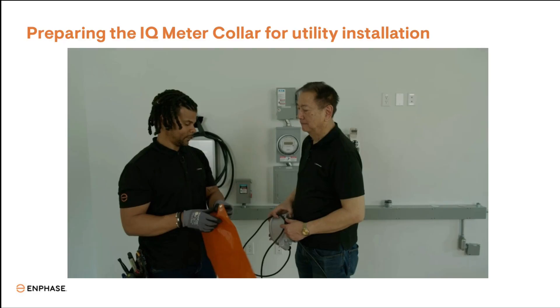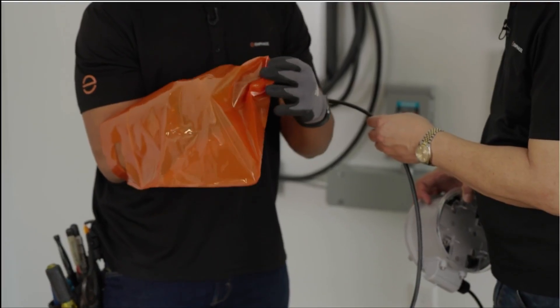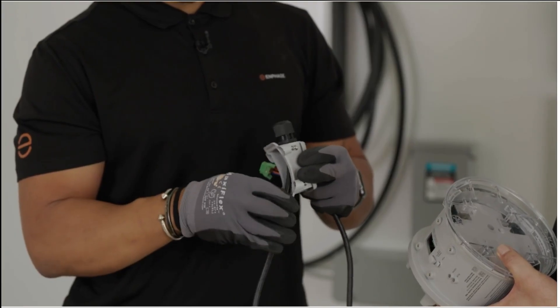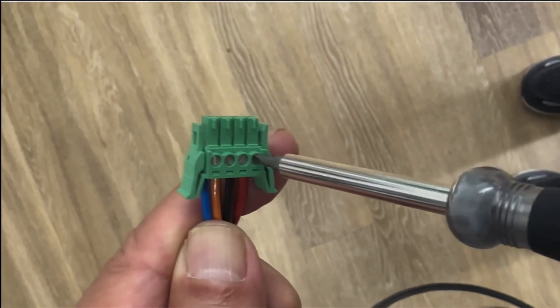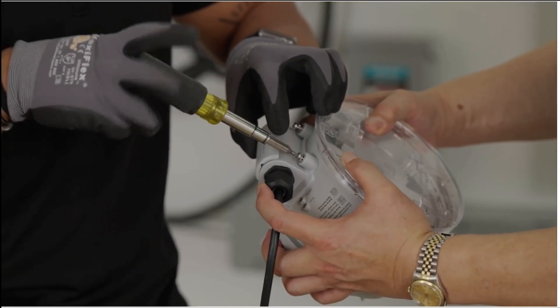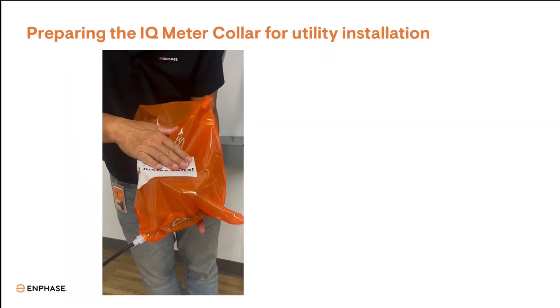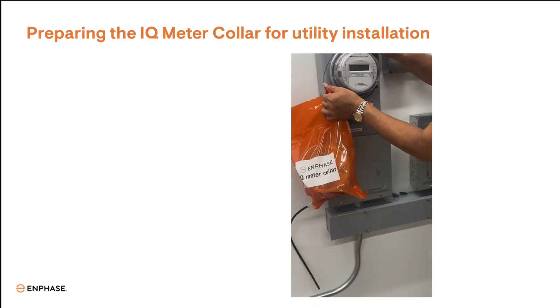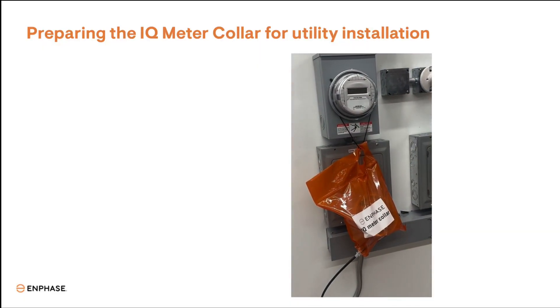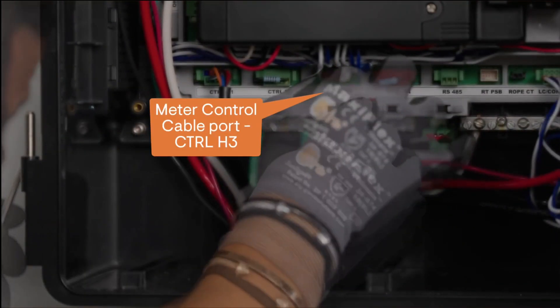Preparing the meter collar for utility installation: run Enphase Control Cable to the meter collar and through the gland in the provided orange high visibility bag. Route the control cable through the meter collar junction box, wire it to the 4-pin connector, and plug it into the meter collar. Install and seal the meter collar junction box. Place the meter collar into the bag and seal it with the collar inside. Hang the bag in a location easily identified by utility personnel. Run the meter collar control cable to the Combiner 6C, wire the 5-pin control cable connector, and plug it into the red Combiner 6C meter collar port.